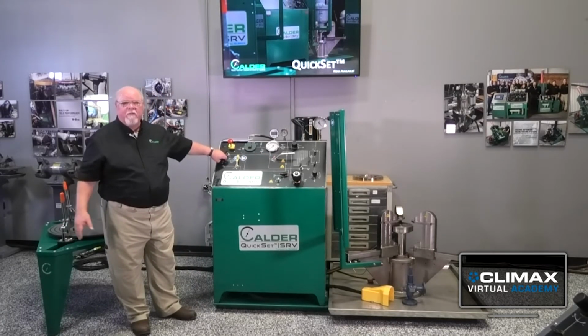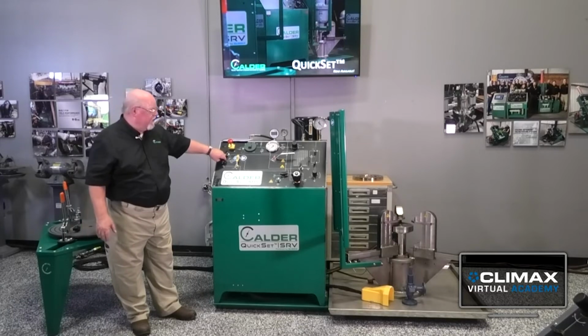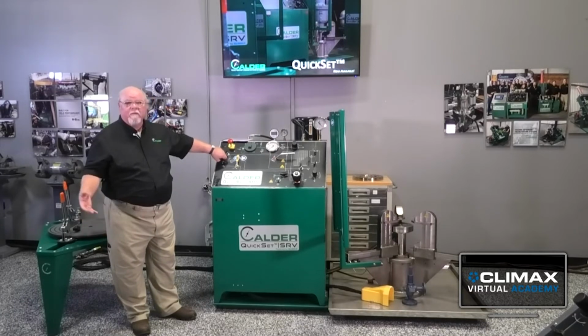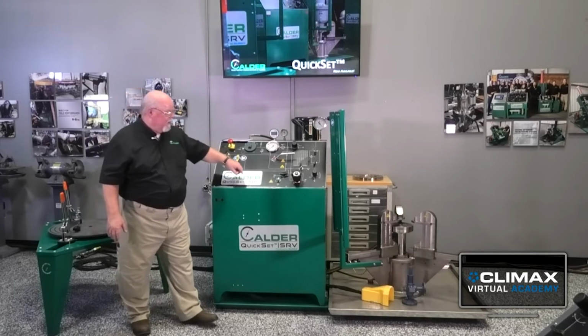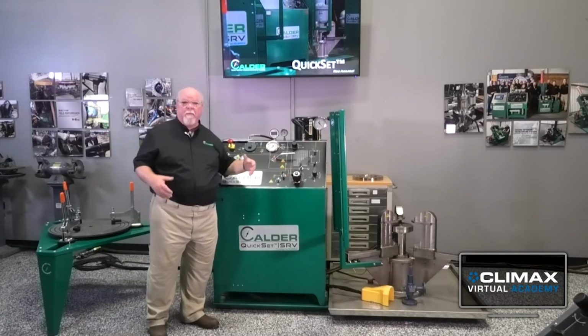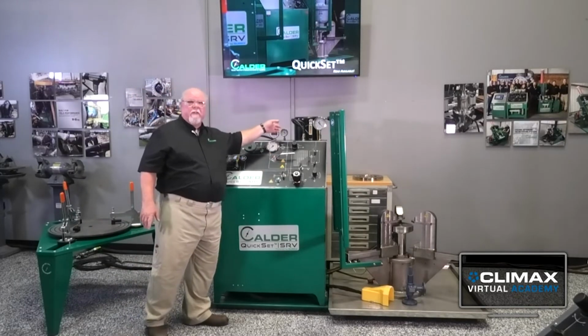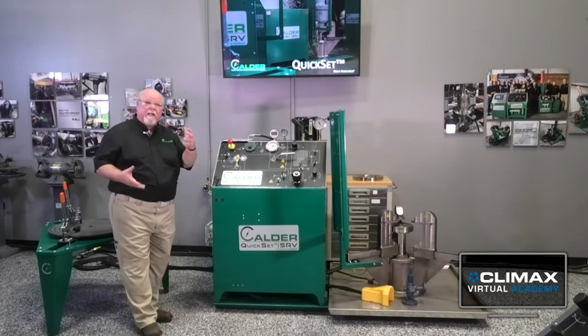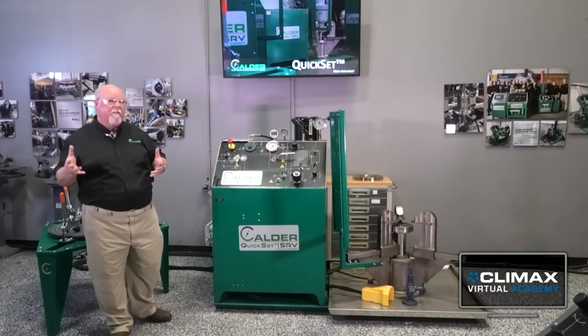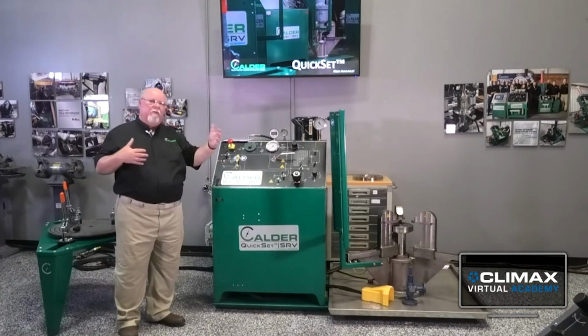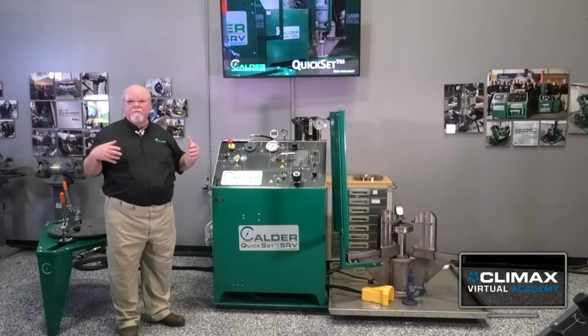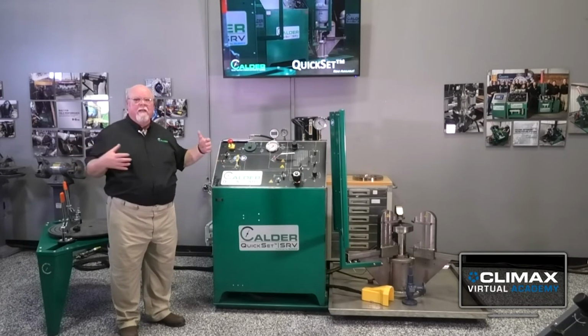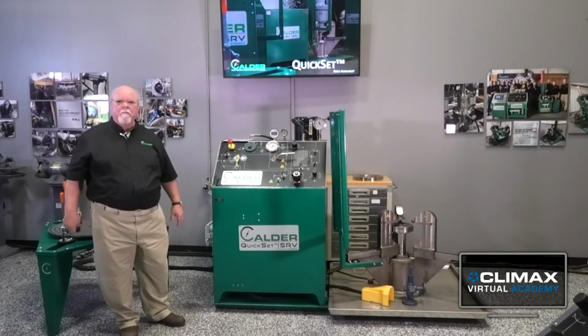Basically what I'm doing is taking shop air, 100 psi shop air, and building up high pressure test gas and storing it in a vessel that's mounted onto the back. So I can get up to 6,000 psi. It'll take a little bit to get there, but if I'm remote or away from standard shop environments, this gives me a really upgradable field option to produce that high pressure test capability in the field as well.